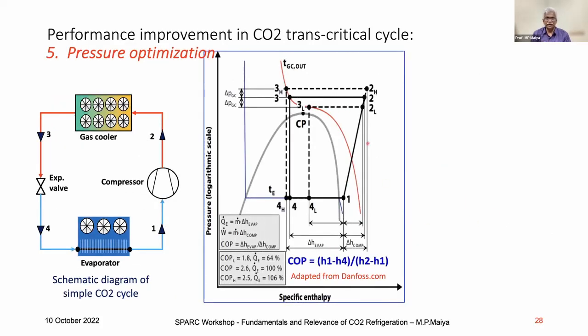Pressure optimization: you can see the conventional refrigerants are in the subcritical region, two-phase, where either pressure or temperature is independent and only one is independent, the other is dependent. Once you fix the pressure, the condensation temperature is fixed. But here we are operating above the critical point, so both pressure and temperature are independent. You can play around. For the same ambient temperature or gas cooler exit temperature, I can find what is the optimum pressure.